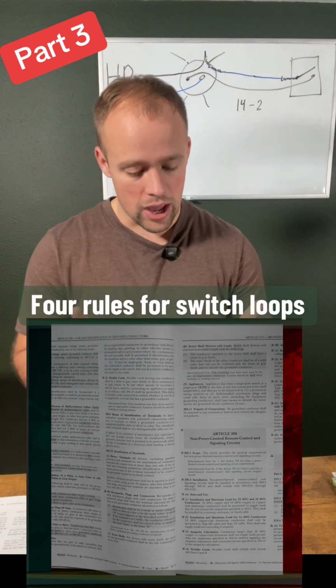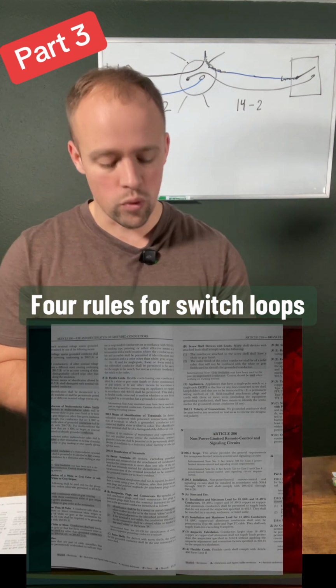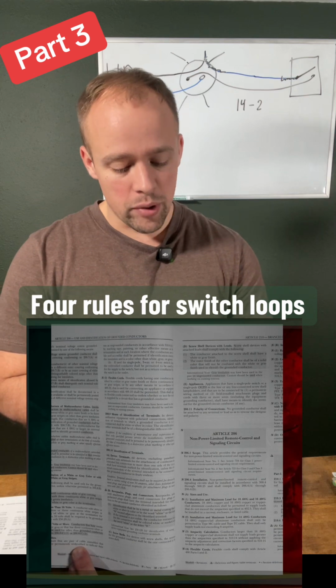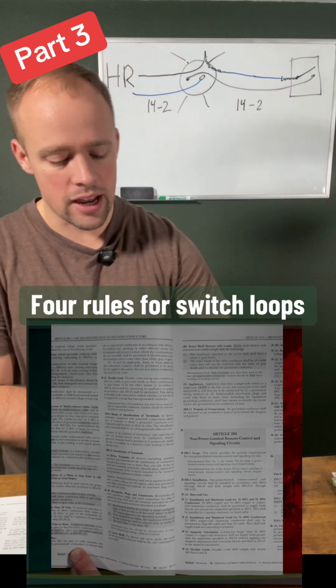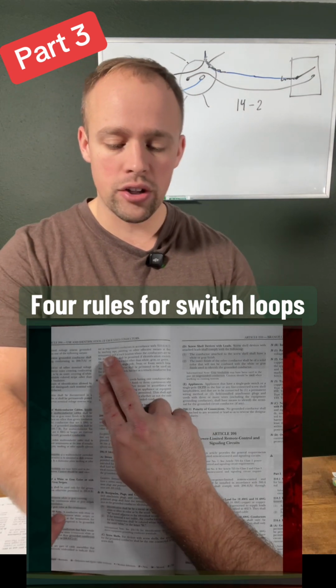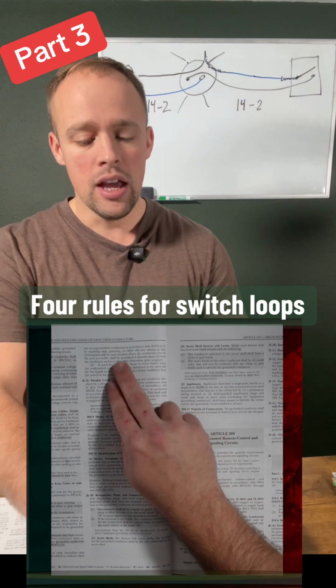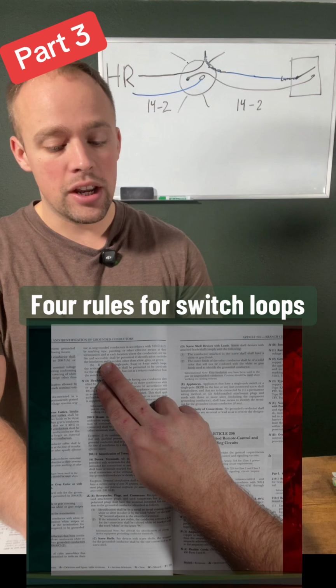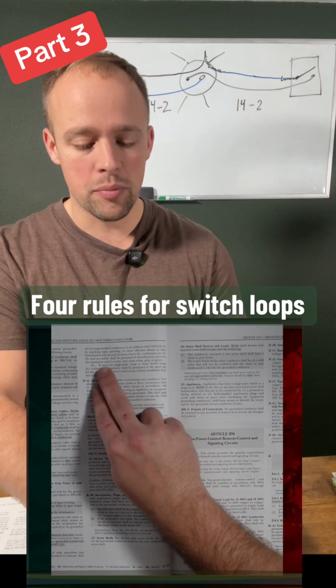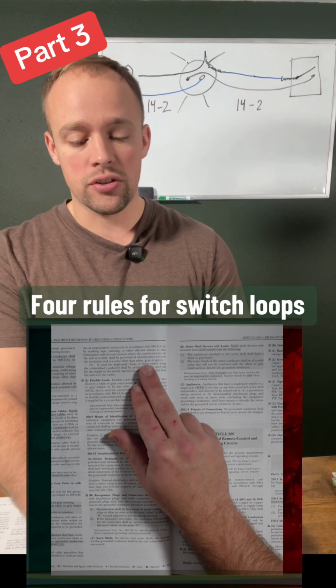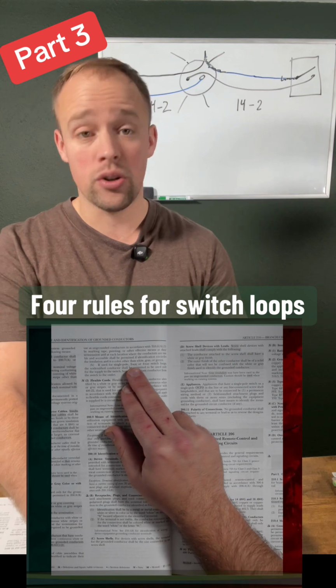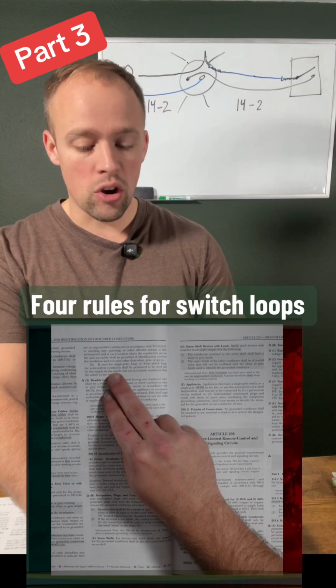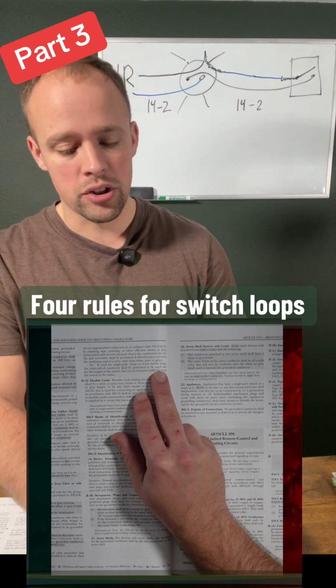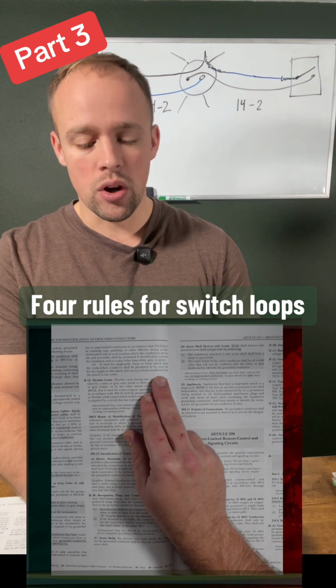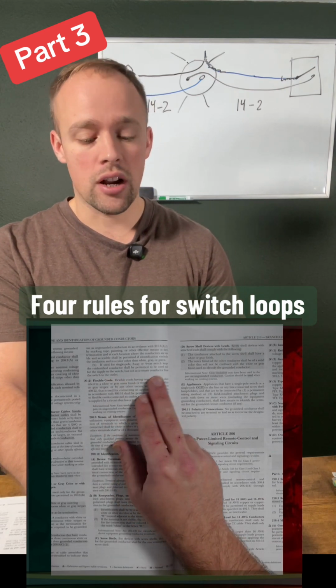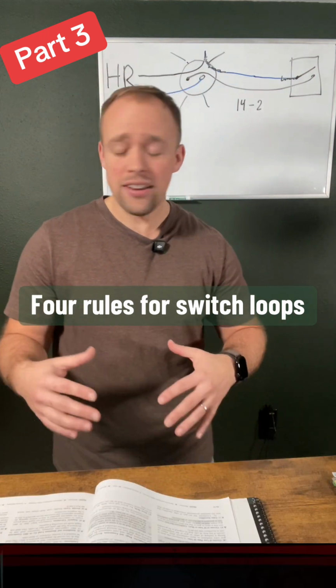So cable assemblies. Okay, so I'm just going to go ahead and read it, and then I will discuss the 4 rules. So conductors that are a part of a cable assembly that have the insulation permanently re-identified to indicate their use as ungrounded conductors in accordance with 310.6a3 by marking tape, painting, or other effective means at their termination and at each location where the conductors are visible and accessible shall be permitted if identification encircles the insulation and is a color other than white, gray, or green. Okay? If used for single pole, 3-way, or 4-way switch loops, there's the word switch loops, the re-identified conductor shall be permitted to be used only for the supply to the switch, but not as a return conductor from the switch to the outlet. Okay, so that is pretty straightforward.